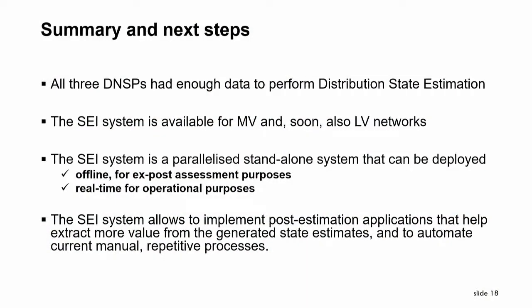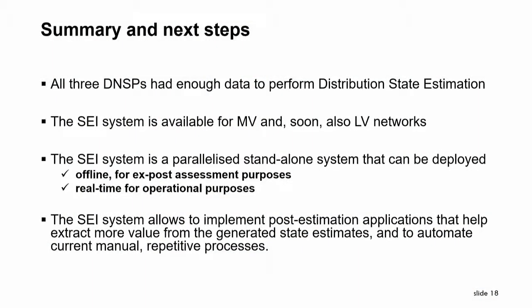So, summary: all three DNSPs, which I think are reasonably representative of what's out there across Australia at least at the MV level, had enough data to perform state estimation. The quality actually surprised us a lot, especially when it comes to voltages. The SEI system is currently available on MV and will be extended to LV. It's a parallelized system that can ingest time series data for backward-looking processing, but we also have a real-time deployment at Energix that sits in their operational environment, and it allows implementation of a range of different analysis tasks, automated within the system.